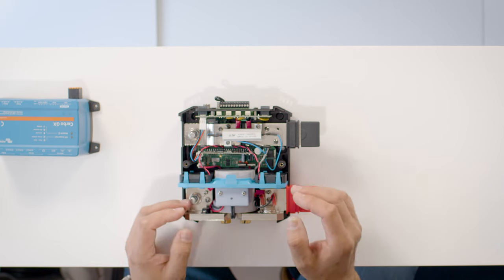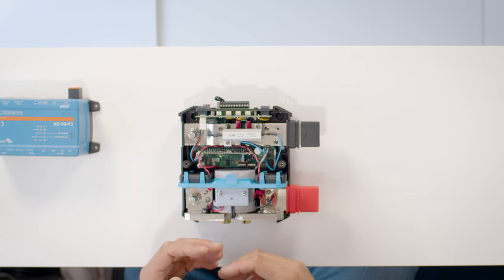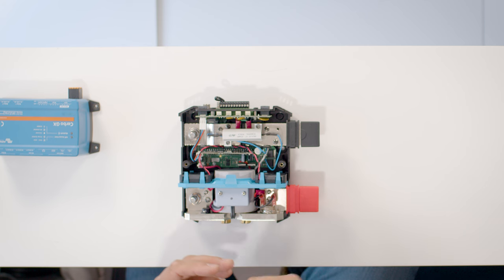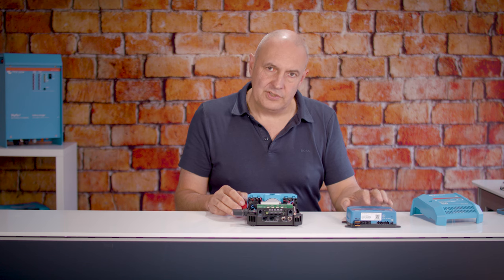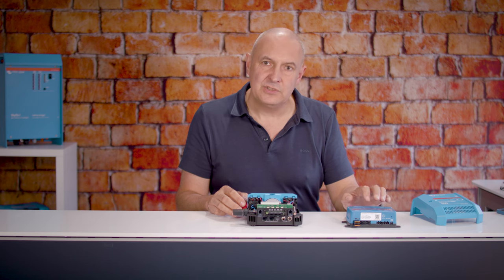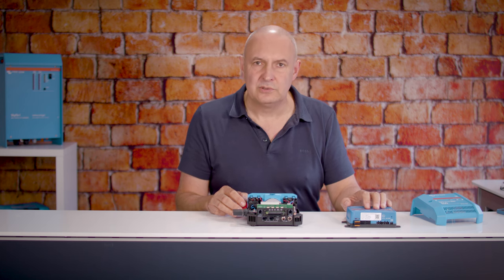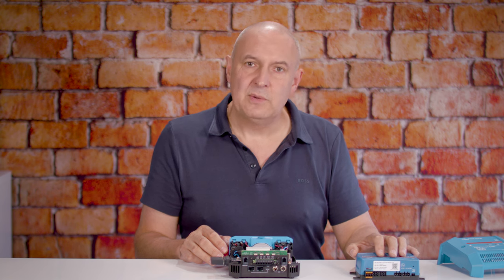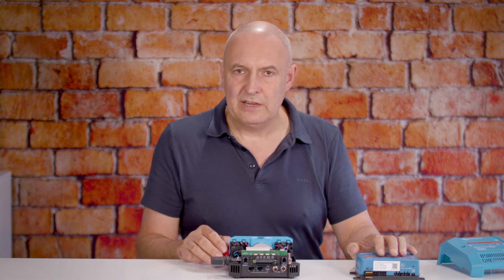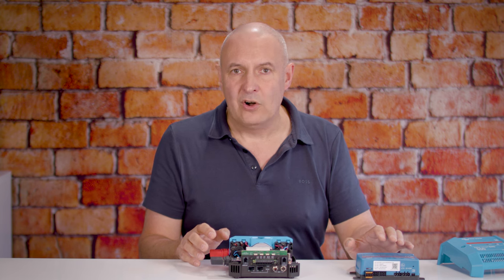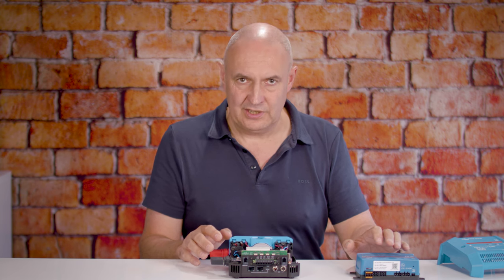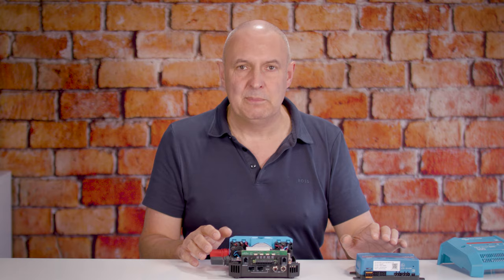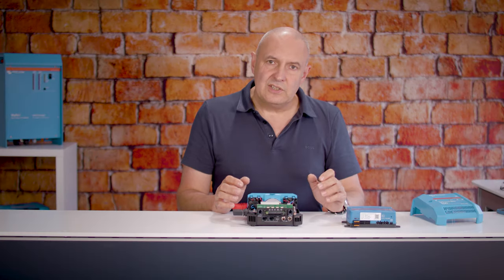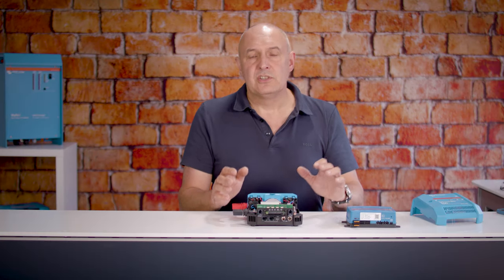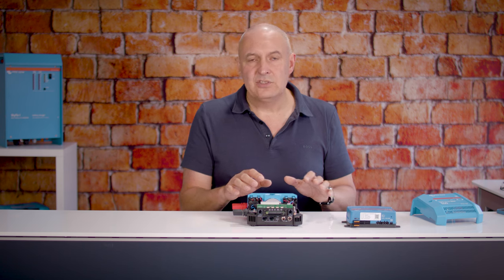And basically it operates in exactly the same way with charging, but it turns off charging sources rather than turning off loads. So the GX device controls everything by enabling DVCC, which stands for Distributed Voltage and Current Control. In reality, this means that the GX device is controlling things in a much more intelligent way. Rather than just turning things on or off, it's controlling the voltages and currents so that we're performing a bit of a balance.